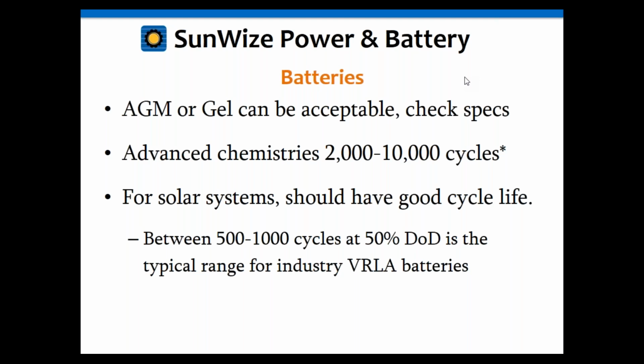There's also advanced stuff out there, lithium-ion batteries and things like that, which supposedly have wonderful cycling life. But if you're taking proper care of your batteries and getting 5 to 8 years out of them, that's pretty good life. How much more do you really need, and is it worth the additional cost? Lithium-ion batteries can be quite expensive, anywhere from 3 to 5 times the cost of a lead-acid battery. So sometimes you have to weigh the initial capital expense against the maintenance expense later on of replacing lead-acid batteries, maybe 5 to 8 years down the road.